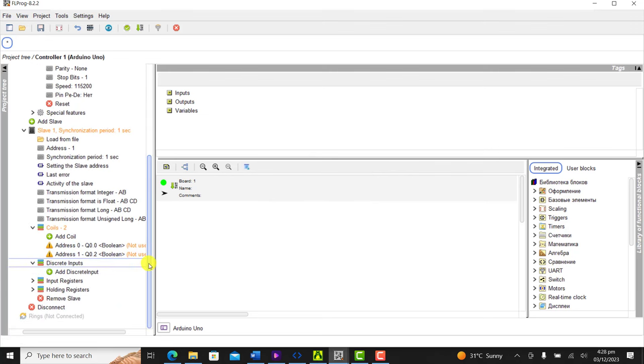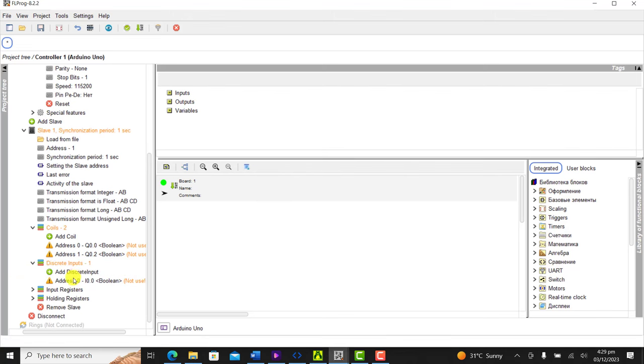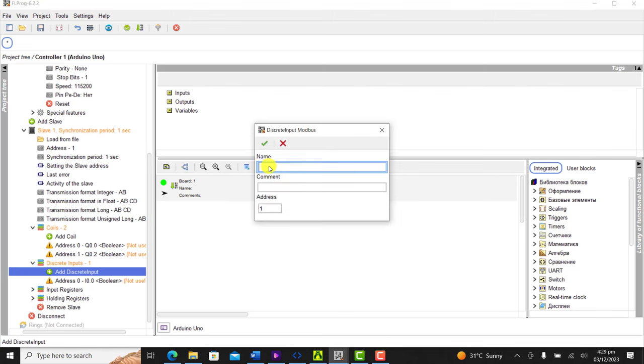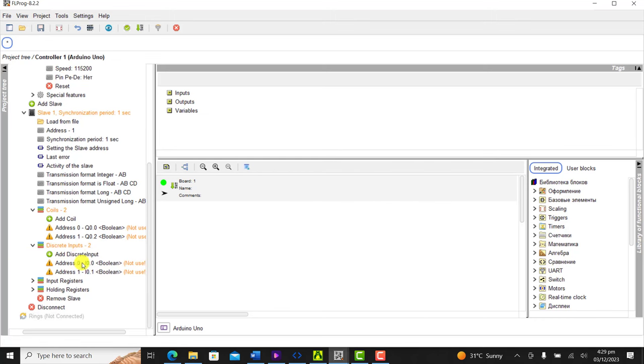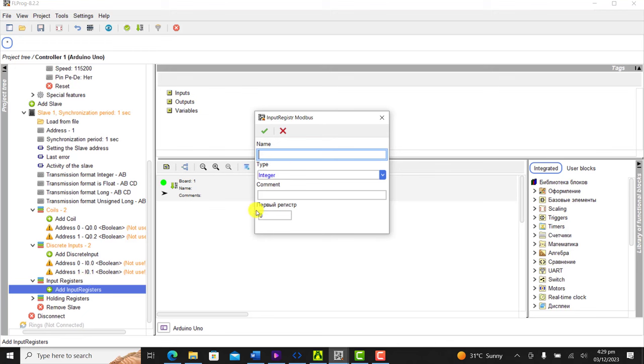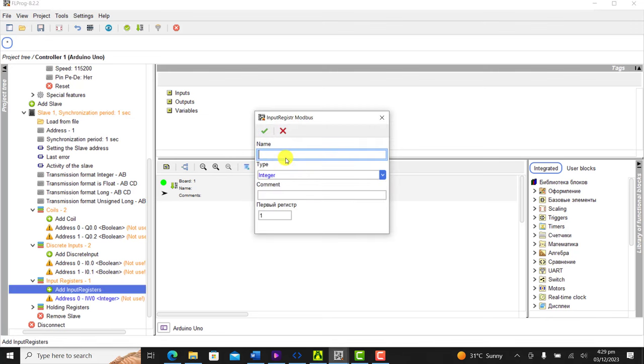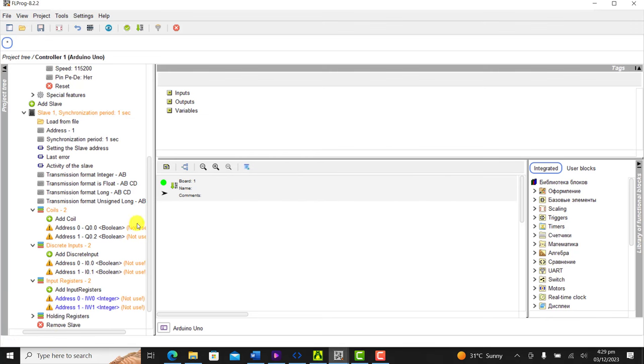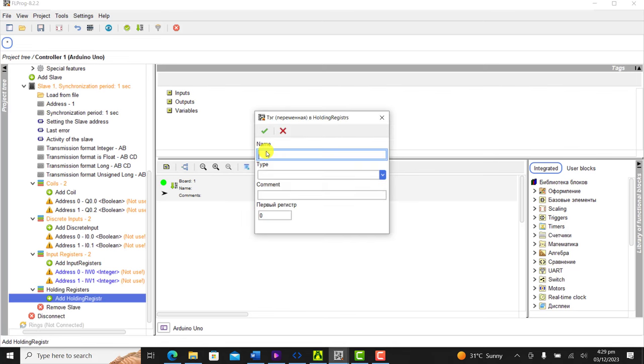We now set our discrete inputs: I0.0, click OK, and I0.1, click OK. We now set up our input register, IW0. Our next address is IW1. We do our holding register: QW0 integer and then QW1 integer as well.